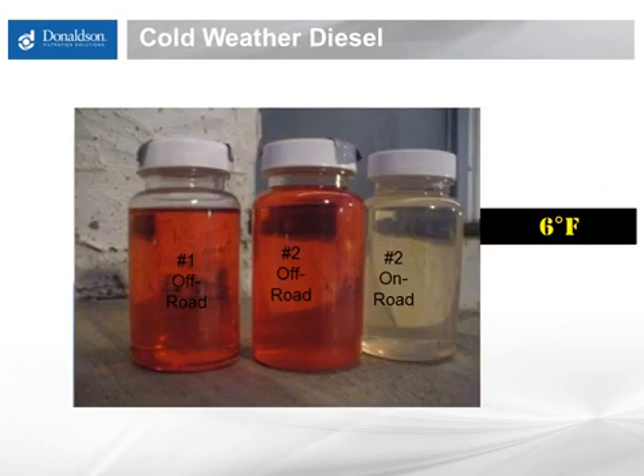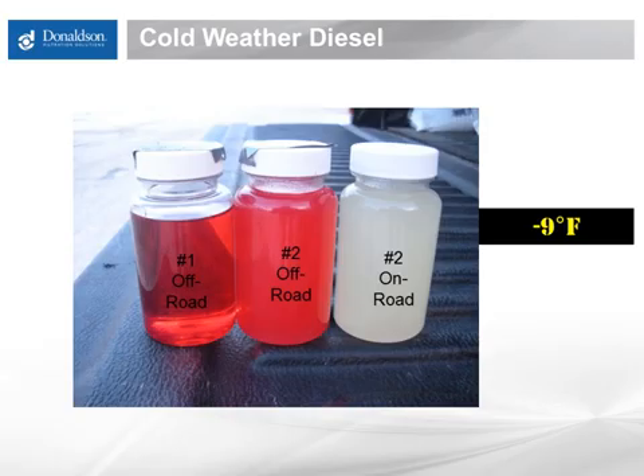This slide makes the practical difference between number 1 and number 2 diesel clear. We have three sample bottles of typical fuel here — the sample on the left being number 1 off-road, the middle being number 2 off-road diesel, and the third being number 2 on-road diesel. At 6 degrees Fahrenheit, all three samples are above their cloud point and ready for use. As the temperature drops, the number 2 diesels are now below their cloud point at negative 9 degrees Fahrenheit, with obvious clouding in both sample bottles. Remember, in winter, a 15-degree swing is not that significant. As fuel in tanks gets colder, it will gel up both in the bulk storage tank and on equipment as well.